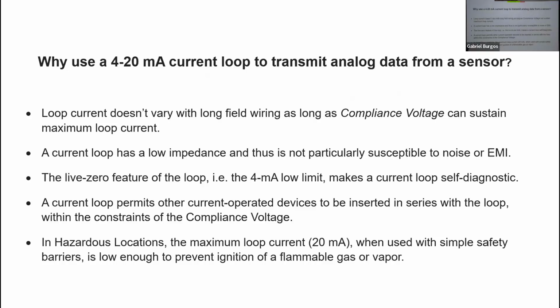Why do you use one in the first place? Okay, number one, the loop current doesn't vary with long field wiring. The resistance of the field wiring doesn't matter as long as you're below the compliance voltage of this loop. What's the compliance voltage? It's the sum of all the voltages that you use up compared to the loop supply.